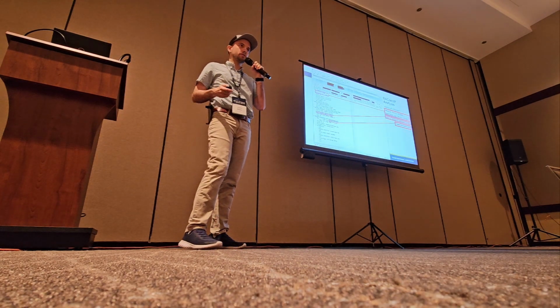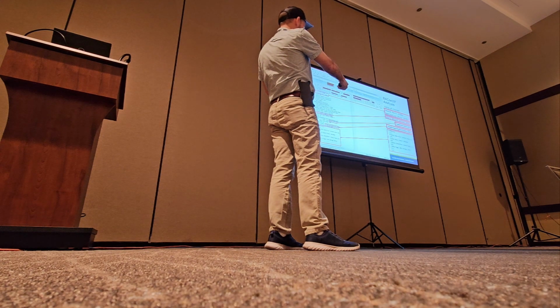All right, so we can see this packet is a complex ACK, which means that multiple pieces of information are being returned as a result of a request that occurred. The request was read property multiple, and here we can see the data that's being returned. In this case, the property identifier is present value, so we have a present value of 10 million something. And the second value has a data type of status flags, and then the value is FFFF.